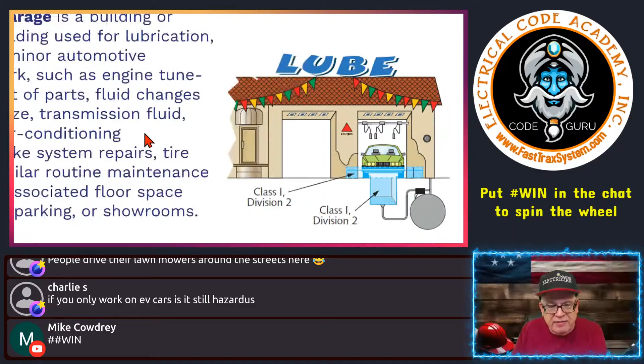If it's going to be somewhere that drains gas or volatile, flammable liquids, or can generate volatile vapors, you just know it's going to be Class 1 Division 1, unless you can do something with the air exchange and get that rating down, okay?